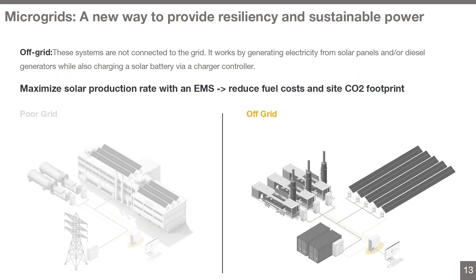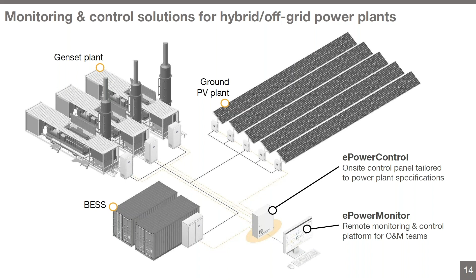Here we just need to integrate with a battery PCS. The system is wired directly to the battery PCS, and our e-power control autonomously manages the site. In terms of features, we manage spinning reserve and do spinning reserve optimization using the batteries, and we still do minimum genset loading. When possible, depending on the genset controller on site, we can even apply a diesel-off mode to save as much fuel as we can.